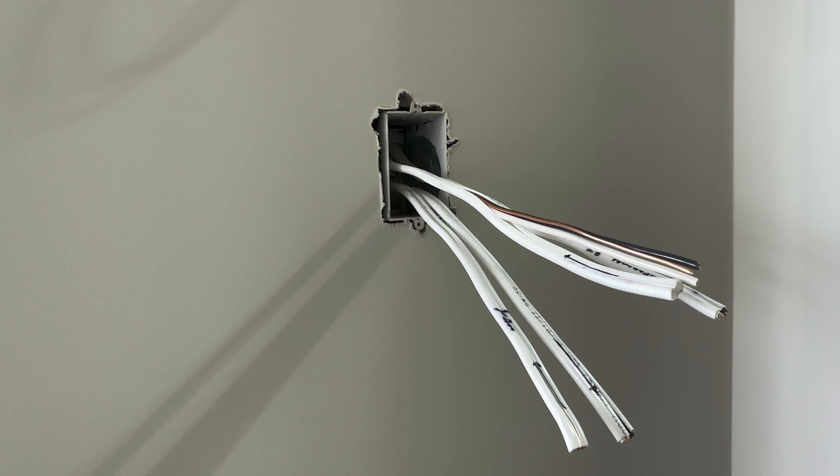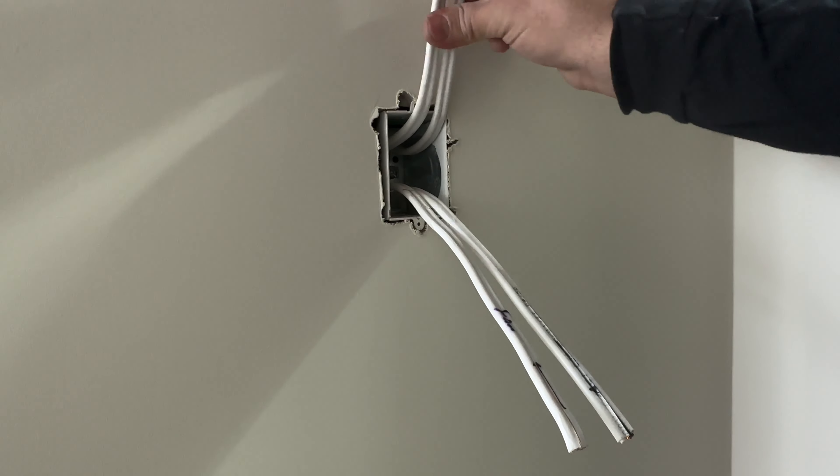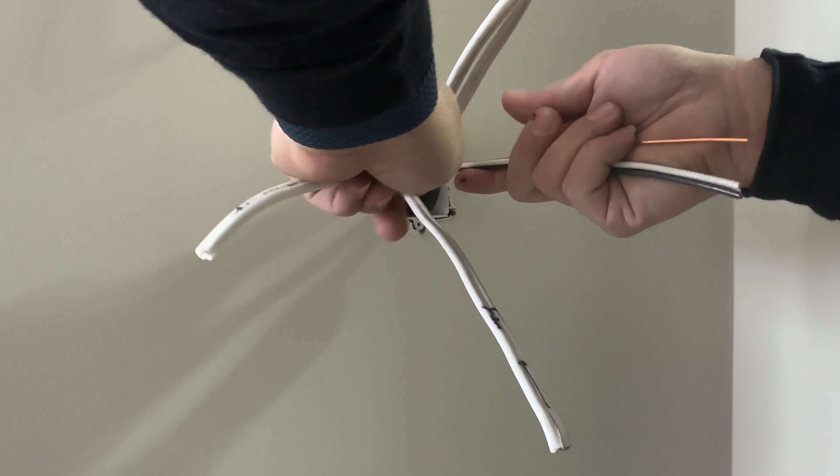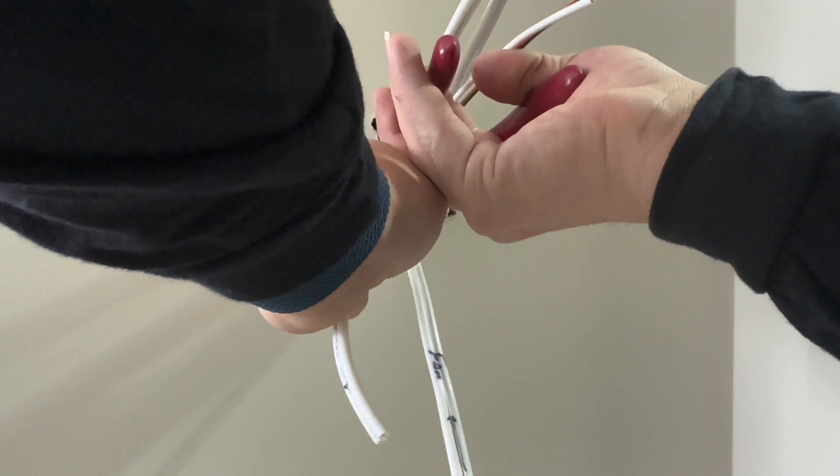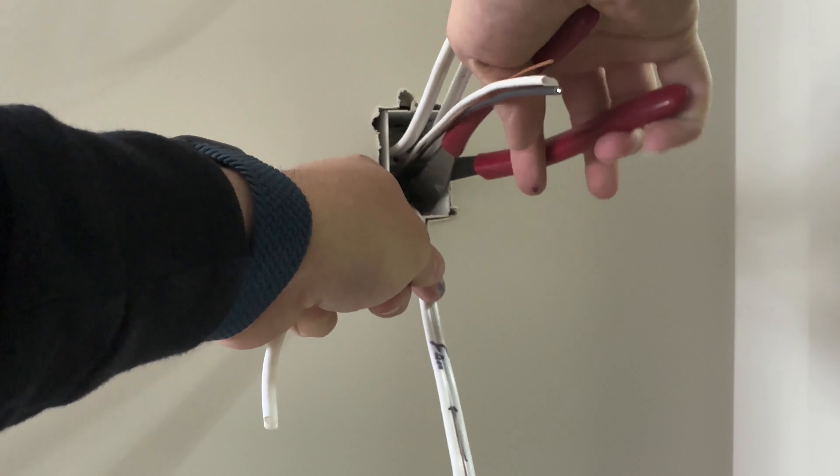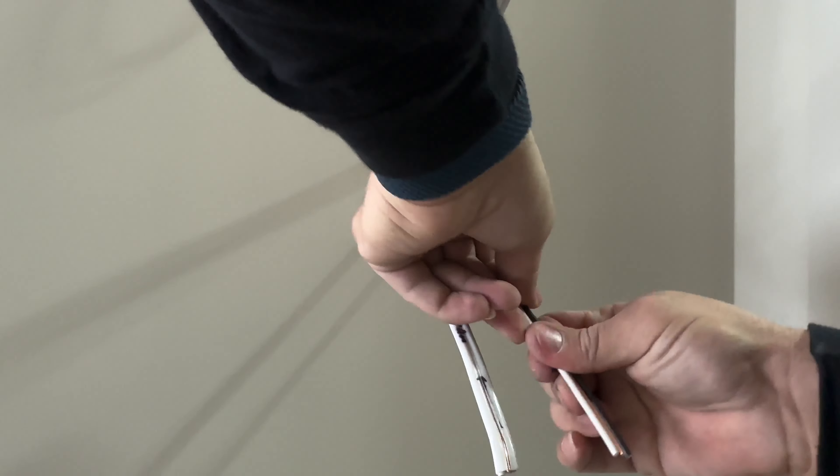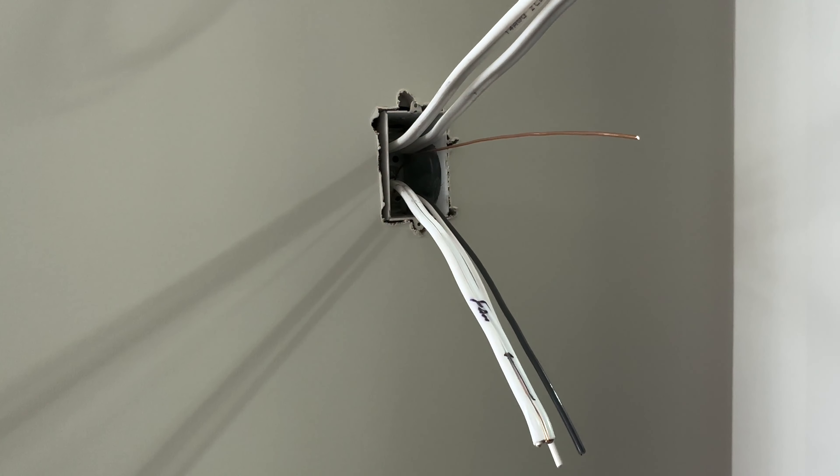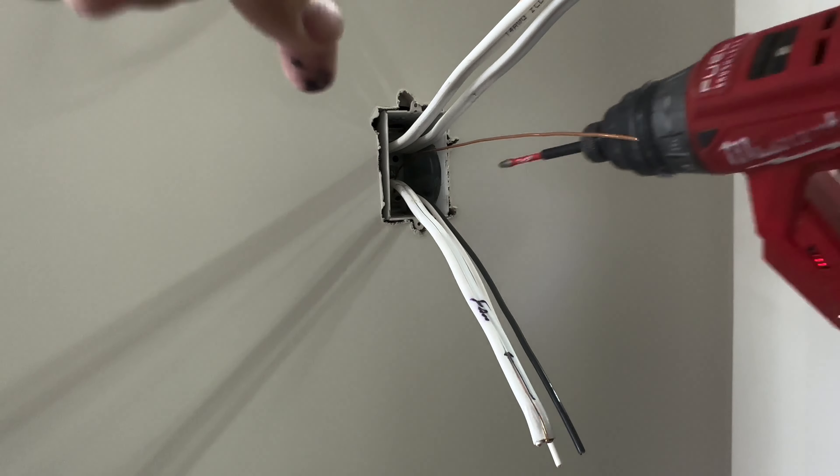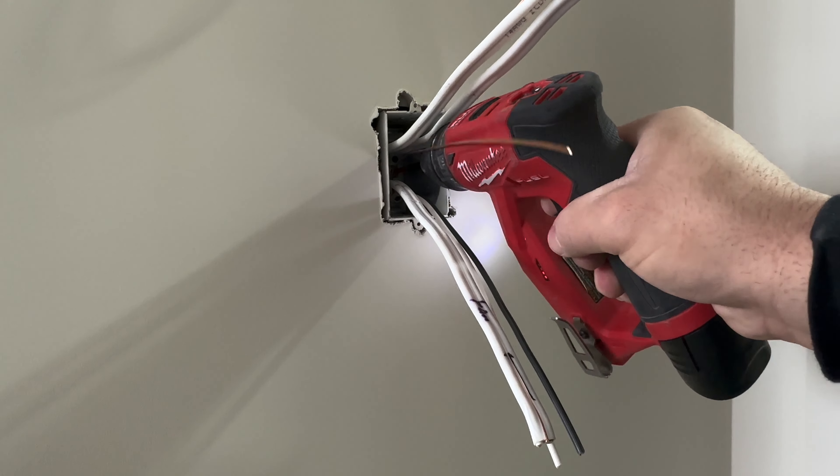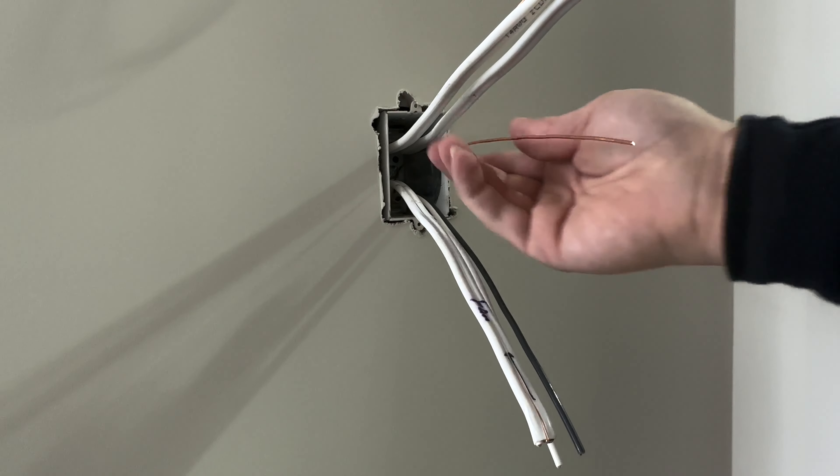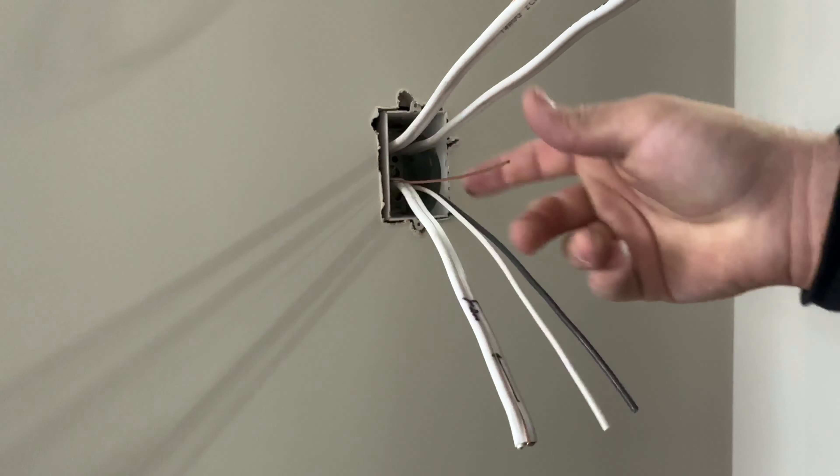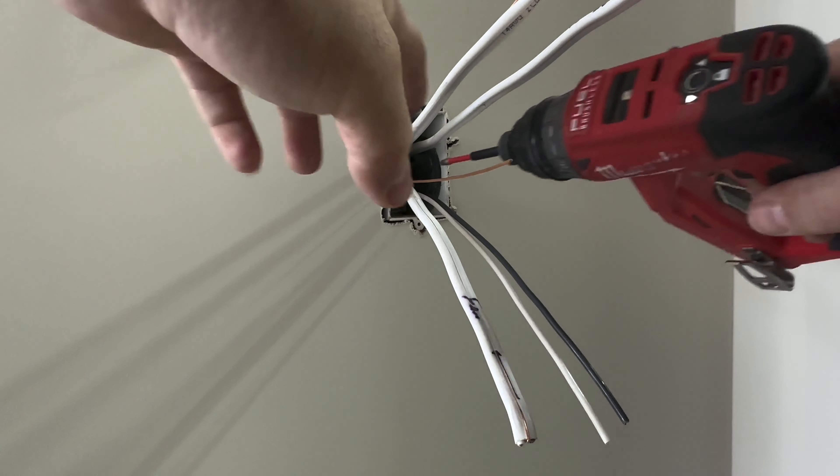We will take one of the ground wires and connect it at the back of the box. If you nick the Romex insulation towards the back with your side cutters, you will be able to pull it out simply. We have our Milwaukee four-in-one driver with Robertson number two. We will wrap the ground wire clockwise around the ground screw on the back of the box.